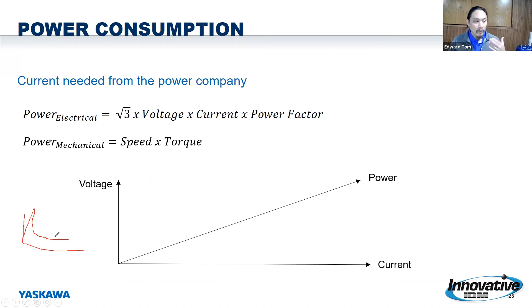Well, if I take the same mechanical equation into effect, I was at zero speed. So if I'm at zero speed and just barely ramping up, guess what? My power, even though I'm putting out 150%, 200% torque to get the unit running, is going to be low, even just to start that motor. I'm not going to see that high current spike that we talked about for across the line. We are going to see a low amount of power being pulled through there as we get the unit up and running and ramped up to whatever speed you're looking for.